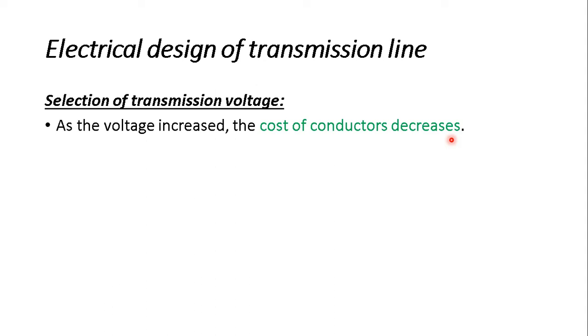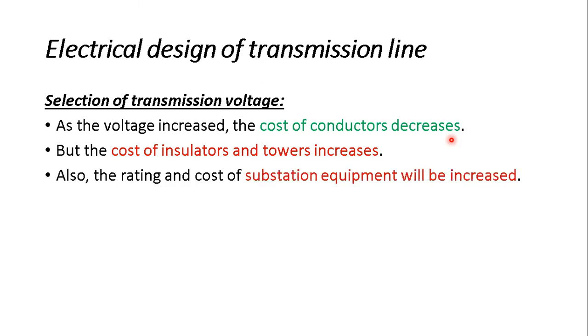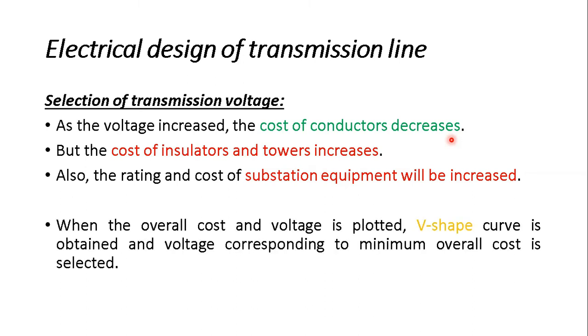As we increase the voltage, the cost of the conductor decreases. However, the cost of insulators and towers increases because the rating and cost of substation equipment such as transformers, switchgear, and protective devices increase. Superior types of insulators in larger numbers are required, and the height of the tower also increases. If we plot overall cost against voltage, a V-shaped curve is obtained, and the voltage corresponding to the minimum overall cost is selected. This is how the selection of transmission voltage is done.